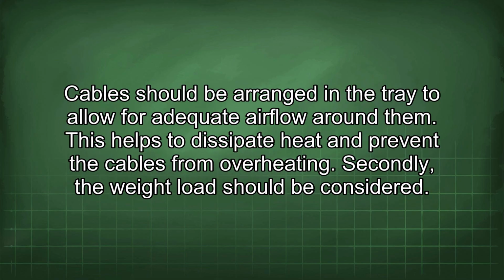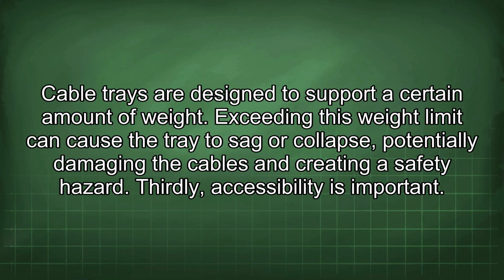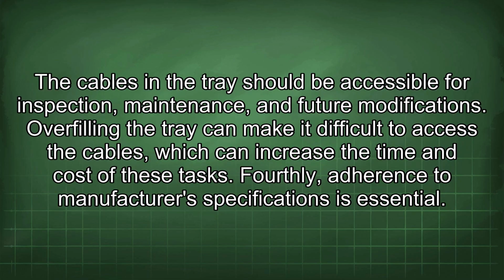Cables should be arranged in the tray to allow for adequate airflow around them. This helps to dissipate heat and prevent the cables from overheating. Secondly, the weight load should be considered. Cable trays are designed to support a certain amount of weight. Exceeding this weight limit can cause the tray to sag or collapse, potentially damaging the cables and creating a safety hazard. Thirdly, accessibility is important. The cables in the tray should be accessible for inspection, maintenance, and future modifications. Overfilling the tray can make it difficult to access the cables, which can increase the time and cost of these tasks.